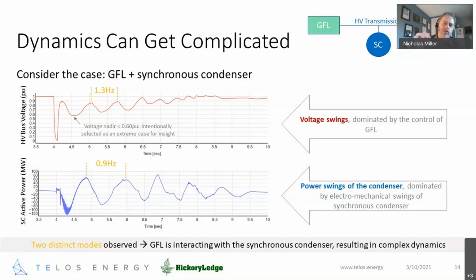So the top one is driven by the control of the GFL. If you had a different control in GFL, you would almost certainly get a different behavior. Maybe that could be stabilized somewhat, but remember, this is a very weak system and is characteristic of running at about the ragged edge of GFL stability. The addition of a synchronous condenser changes that short circuit ratio in a direction that's kind of consistent. It's not quite as effective as making the systemic short circuit ratio better.